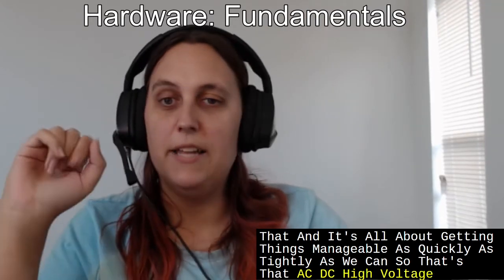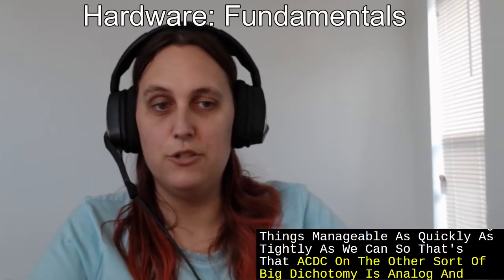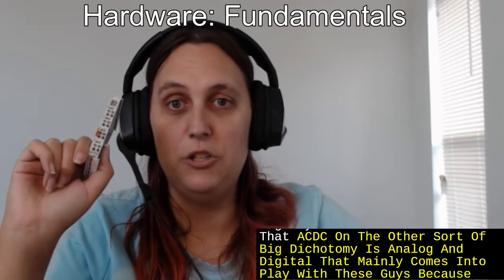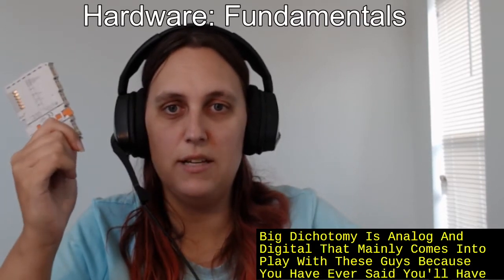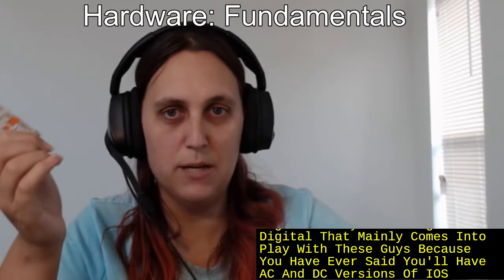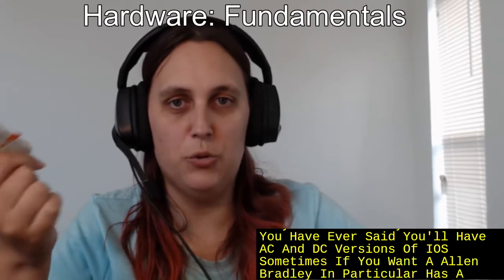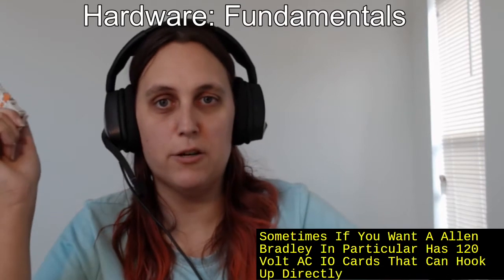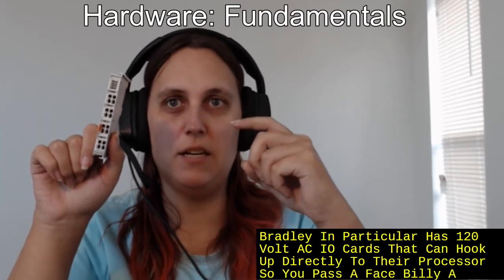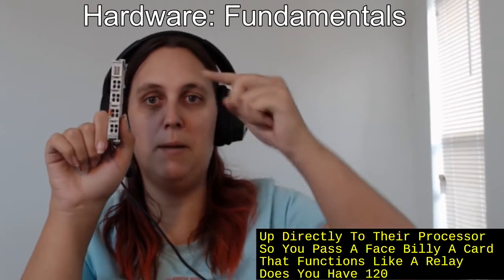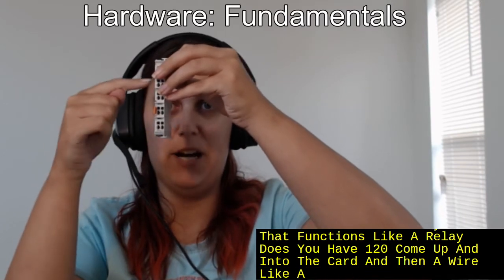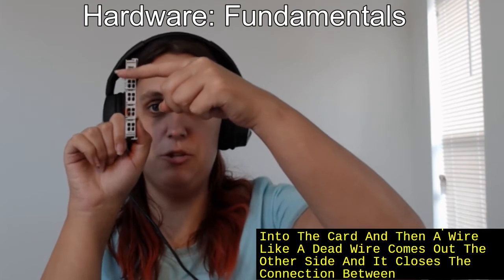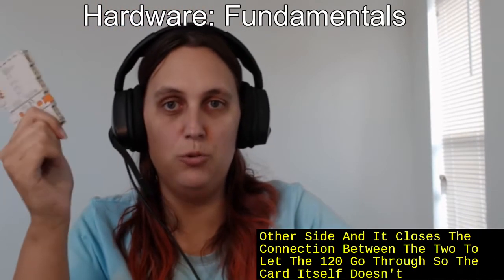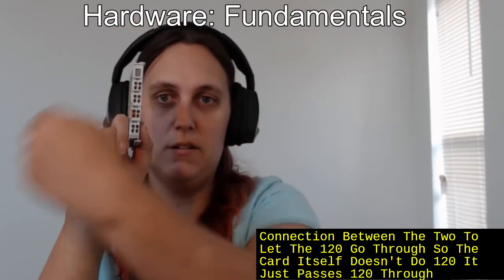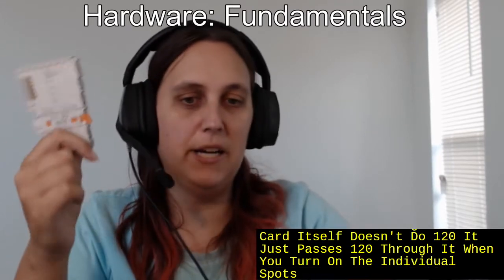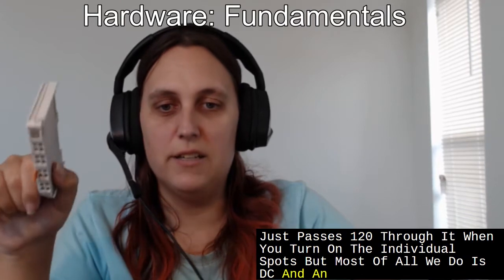AC, DC, low voltage - the other big dichotomy is analog and digital. That mainly comes into play with these IO cards, because you'll have AC and DC versions of IO sometimes. Allen Bradley in particular has 120-volt AC IO cards that hook up directly to their processor. It basically functions like a relay: 120 comes into the card, and a dead wire comes out the other side, closing the connection to let the 120 go through. So the card itself doesn't generate 120; it just passes it through when you turn on the individual spots. But most of what we do is DC, and analog/digital IO.